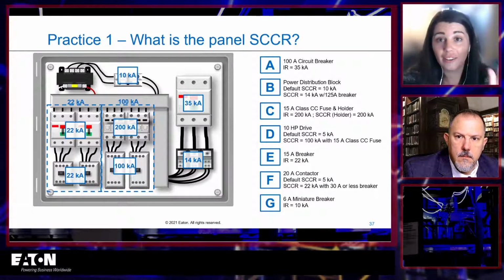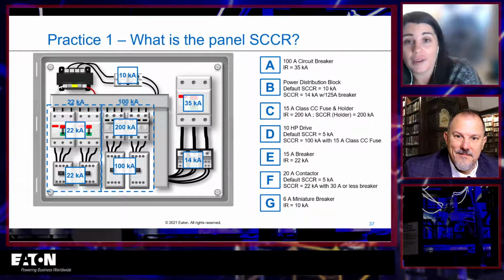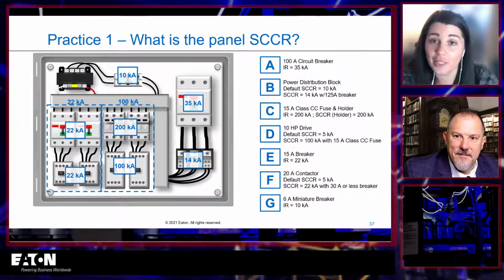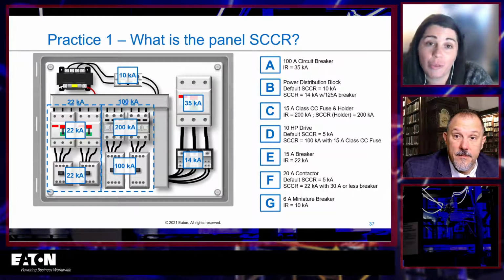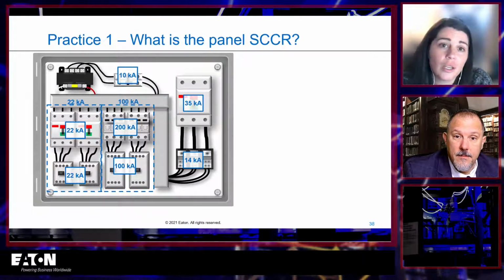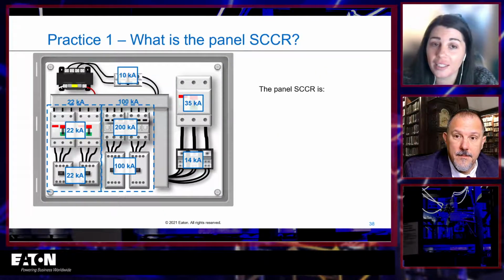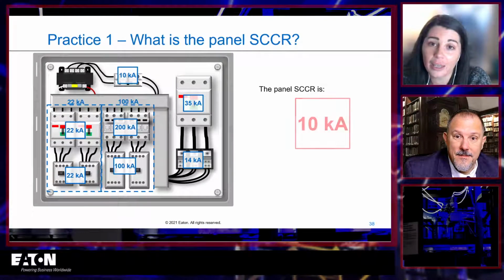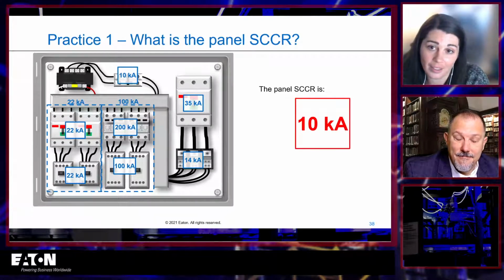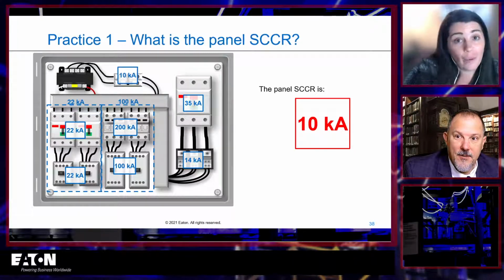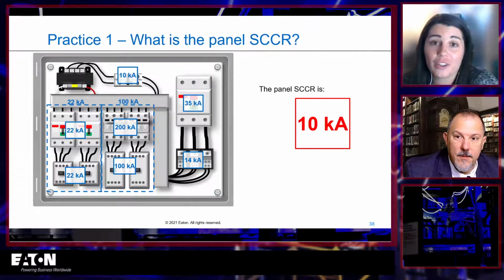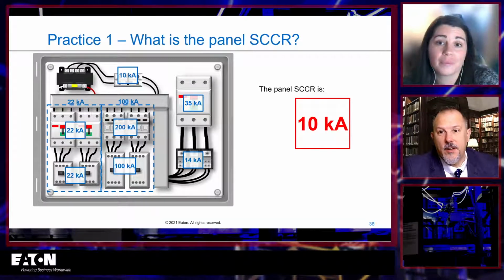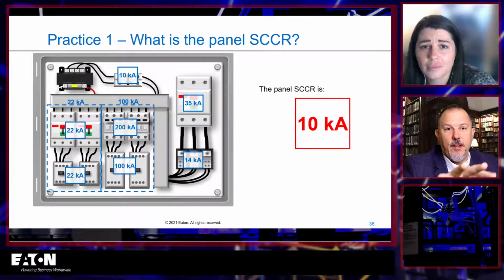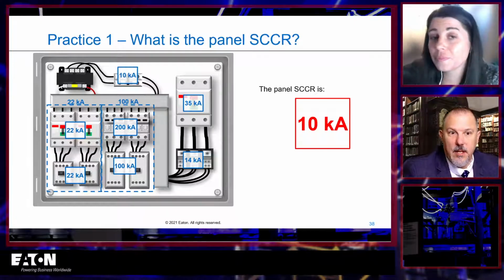And then I get to do step 4. Step 4 is to pick the lowest values from steps 1 through 3. So I've got 35, 14, 10, 22, 100 for the panel SCCR, lowest value there. Last time I checked, 10 kA is the lowest value there. So that is, very generally speaking, how I'm going to determine panel short circuit current rating. So you went through every component, worked your way up, and then you just picked the lowest SCCR.